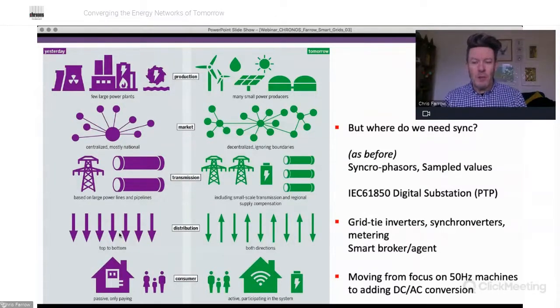Sampled values are used. The digitalization of substations, talked about in the IEC 61850 standard, sometimes called the digital substation, calls for the precision time protocol, PTP, a timing standard, a timing over network standard, also known as IEEE 1588. And lots of generation and grid tie systems require synchronization to the grid for generating voltage that's in phase with the grid.